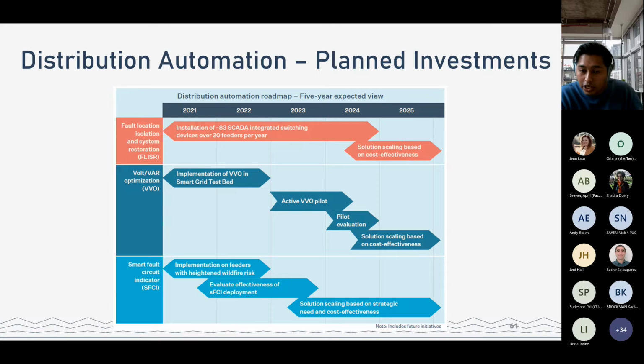We also talk about voltage and reactive power optimization, or volt-var optimization, where fundamentally we are trying to optimize the voltage across the system in a way that causes minimum disruption to the customer while reducing the amount of peak energy needed on the system. That's the balance we try to hit with volt-var optimization.